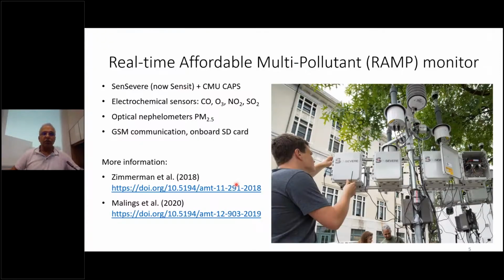So one such low-cost monitor that I'll talk about a lot today is the Real-Time Affordable Multi-Pollutant Monitor, or RAMP, which was developed by my group at Carnegie Mellon in collaboration with Sensevere, a small company in Pittsburgh that is now owned by Sensit, and it's based in Indiana. Just to get this out of the way, I have no financial interest in the company, but we work closely in the development, and I'm probably one of their largest customers for the RAMP monitors. It uses electrochemical sensors for gases: carbon monoxide, ozone, NO2, and SO2. It uses optical nephelometers like a Met One neighborhood PM monitor or a Purple Air monitor or a Plantower sensor for PM measurements. They come with GSM communication and an onboard SD card for local data storage.